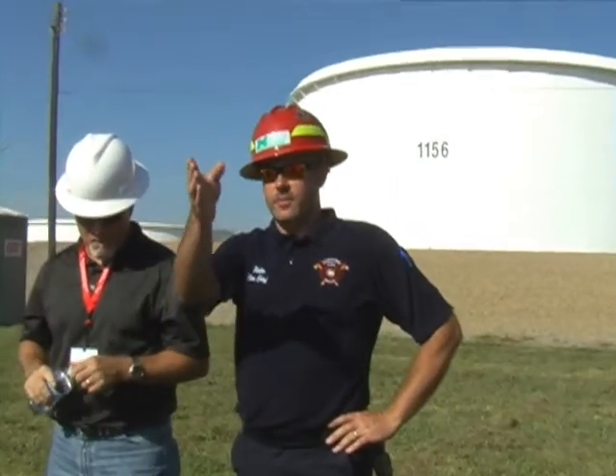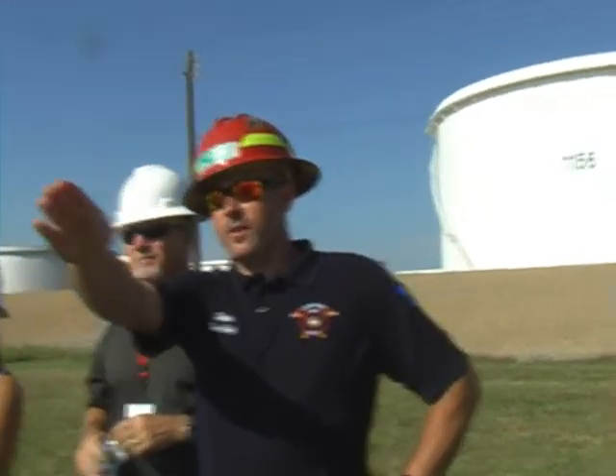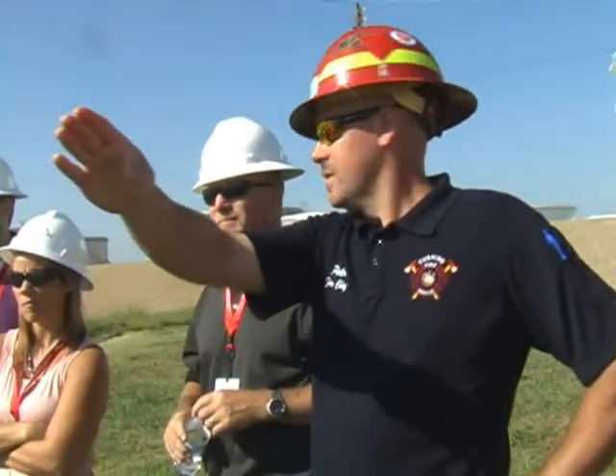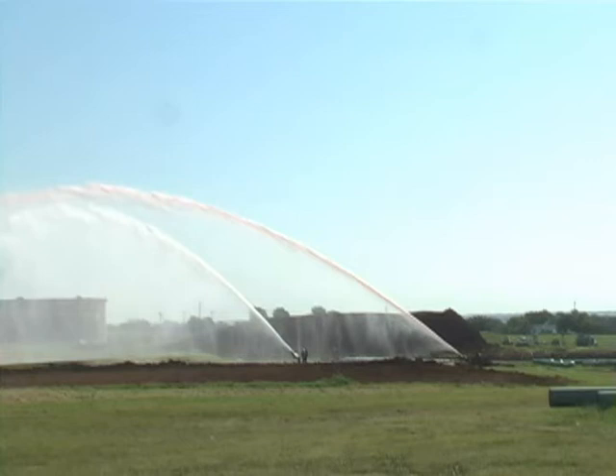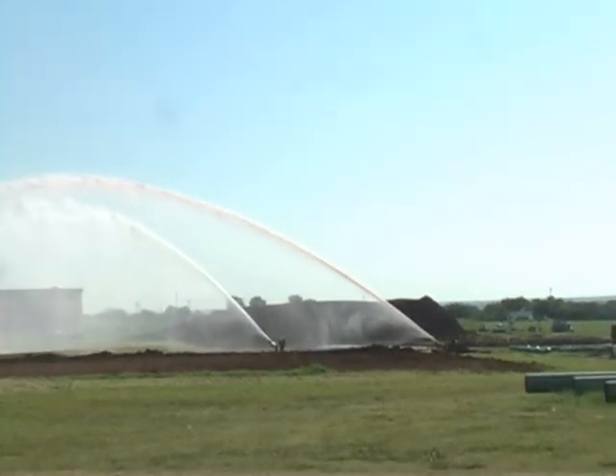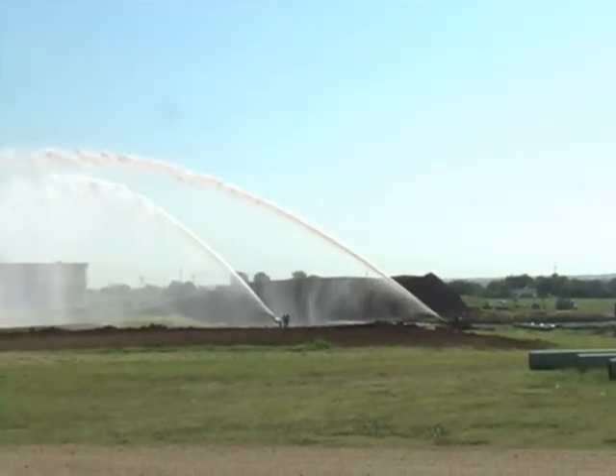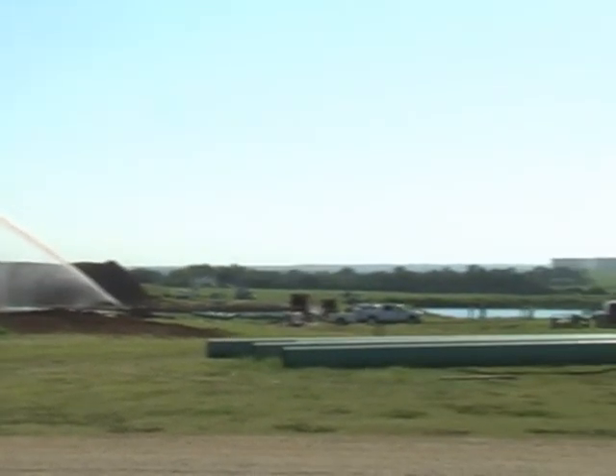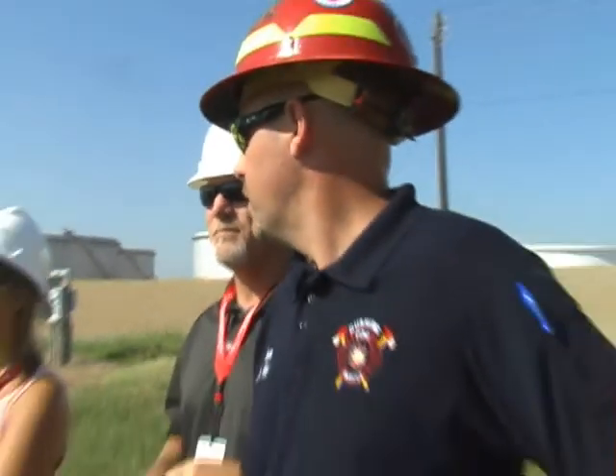These are learning experiences, and one thing that we're dealing with right now is, if you look at these two streams, the red stream you got all the distance and the reach. This front stream you don't. We've got a bad nozzle. So in a real-life situation, we would have been knocking on another door going, hey, can we borrow your monitor and trade this one out for that one so that we had two even streams. For the scenario, a lot of this is to exercise these pumps. We're just going to keep going and continue on.